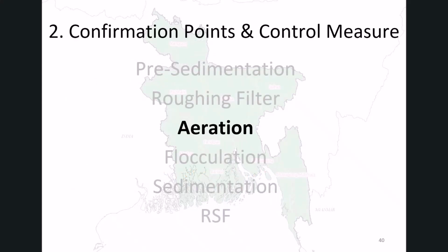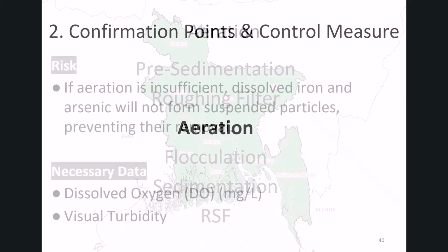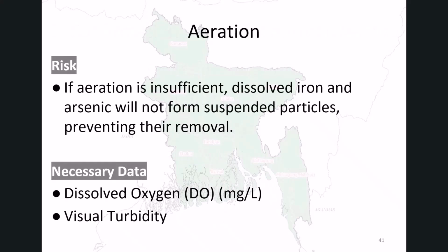Now we go to the aeration part. The first agenda, basic theory. This explains why aeration is essential in groundwater treatment. If aeration is insufficient, dissolved iron and arsenic will not oxidize into suspended particles, meaning they cannot be removed in sedimentation or RSF. So, the major risk is that contaminants remain dissolved and invisible even after treatment.